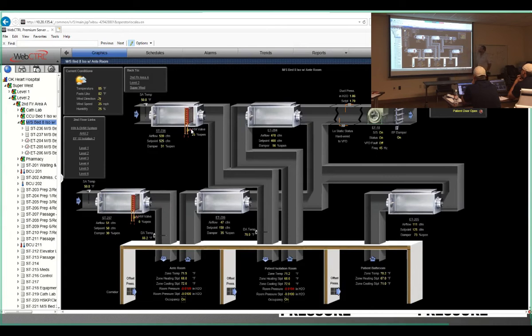The exhaust fan, of course, is kind of self-contained. It's going to maintain a set point, test and balance. Control guys work to set up what that exhaust static needs to be so that we can maintain constant static pressure so the boxes can maintain CFM.